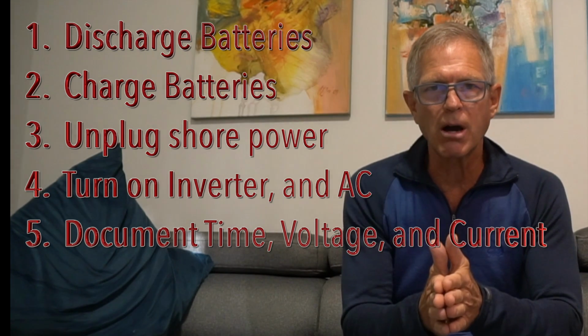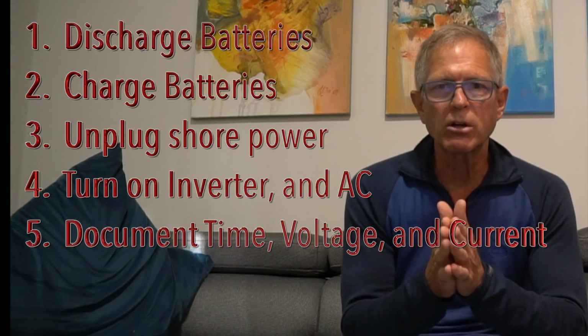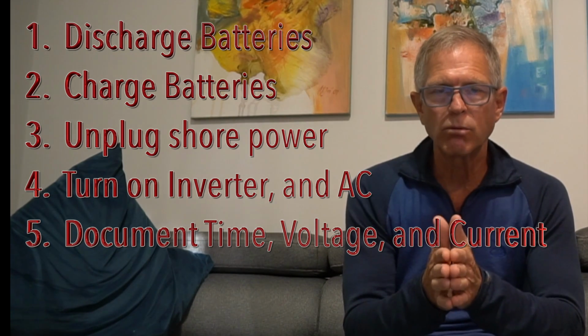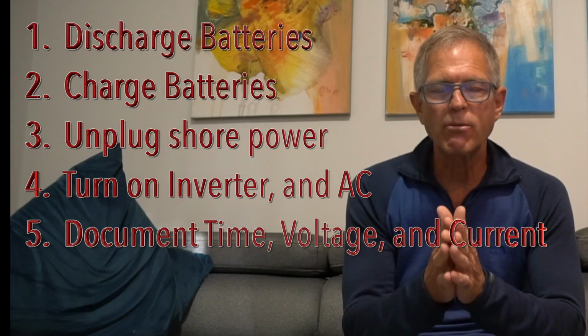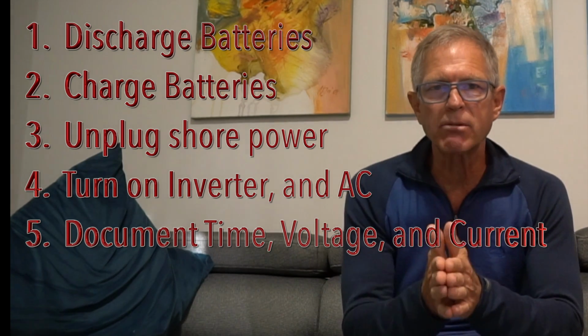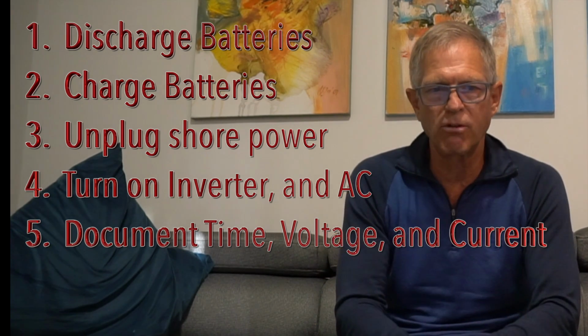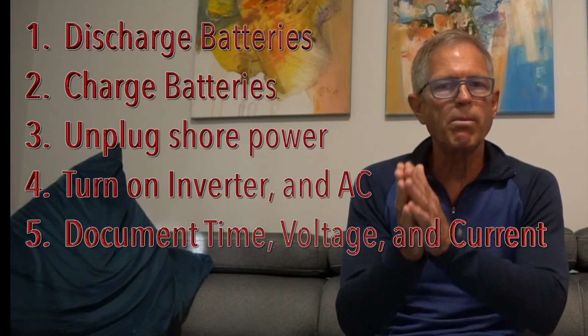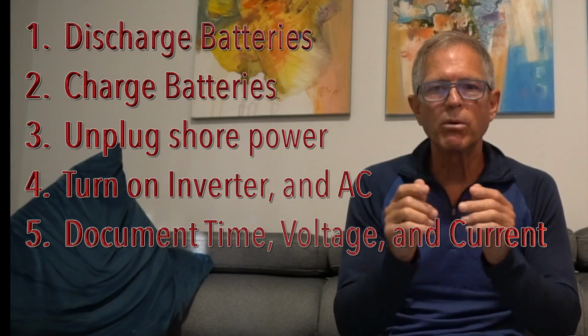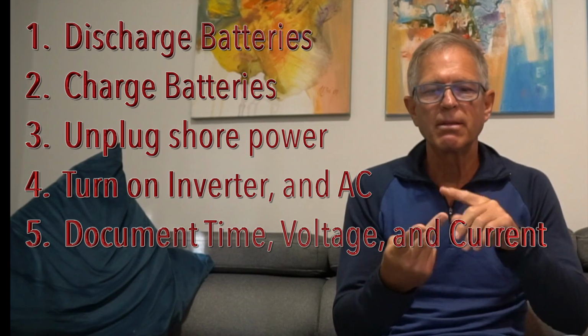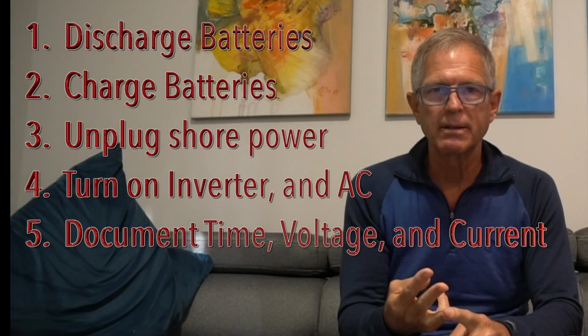We'll turn the inverter on and turn the aft AC on, which is just a plug-in, and run that until we get the batteries back down to about 24 volts. During this whole process, every hour we'll mark down the time, voltage, and current, put that information into a chart, and figure out just how well these batteries are doing.